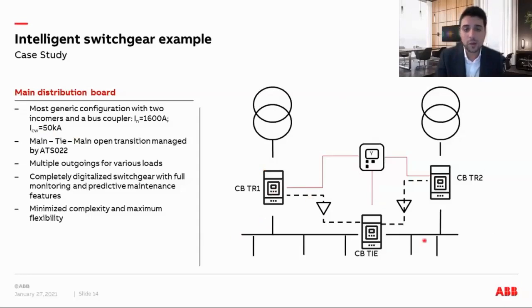We also considered some critical loads, meaning we're able to supply from one or the other source. For this we needed automatic transfer switching between two sources, applying the ATS-022 for main-tie-main open transition. We have multiple outgoings for various loads, and this whole switchgear—Alberto will share more details in a minute—is completely digitalized with full monitoring capabilities and predictive maintenance features.